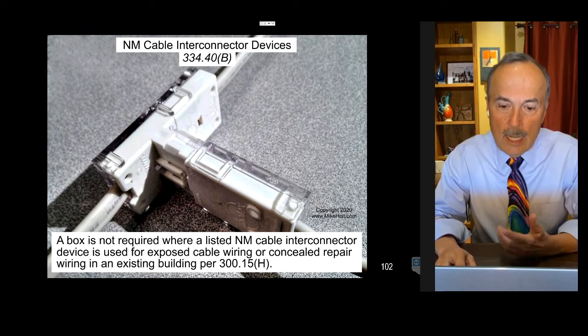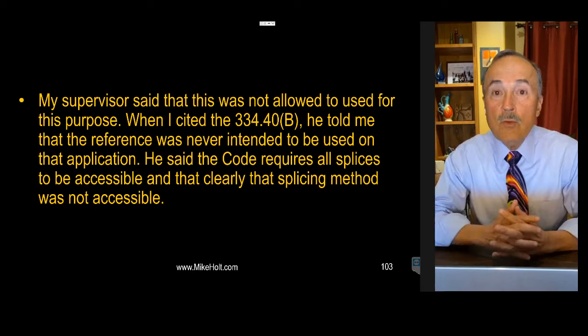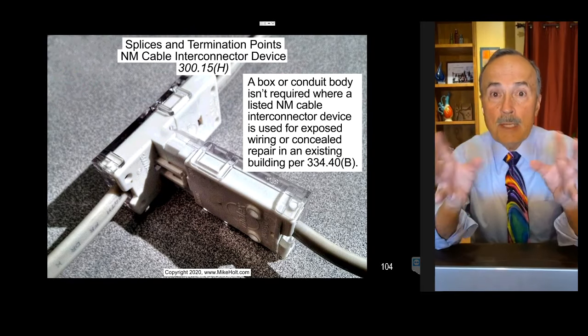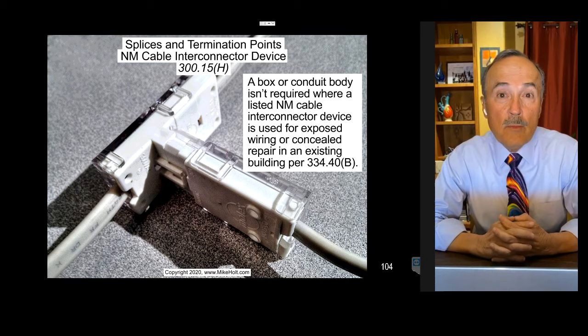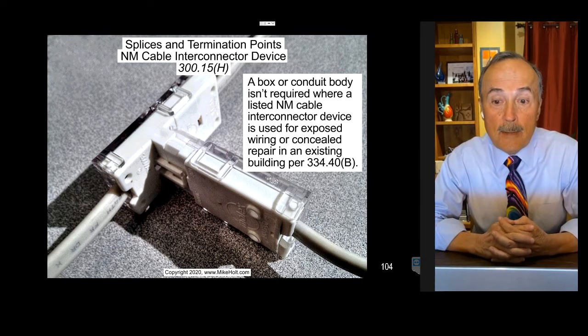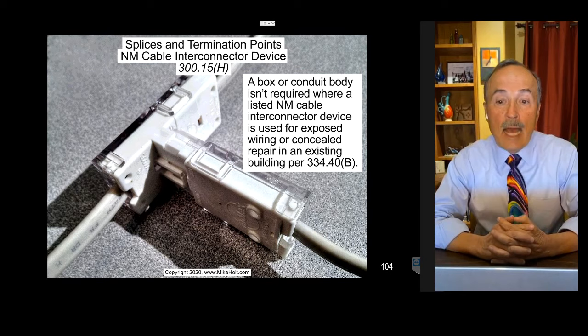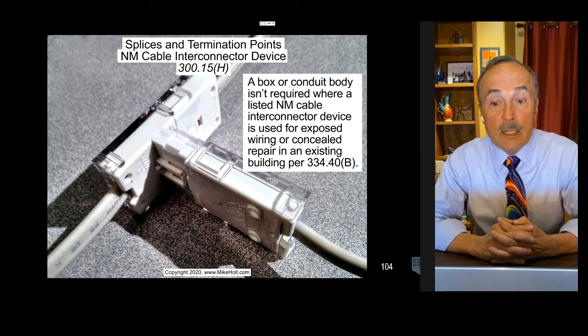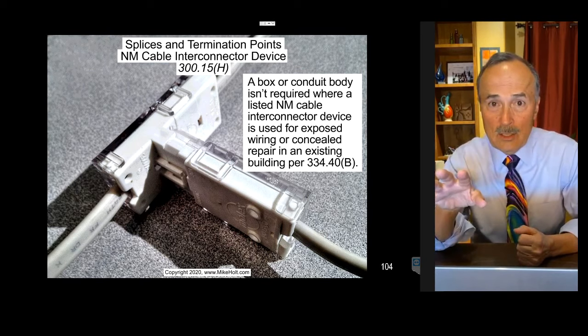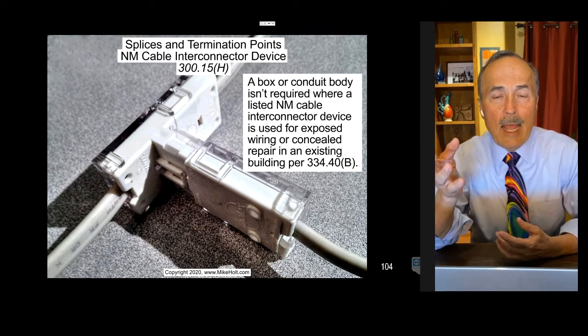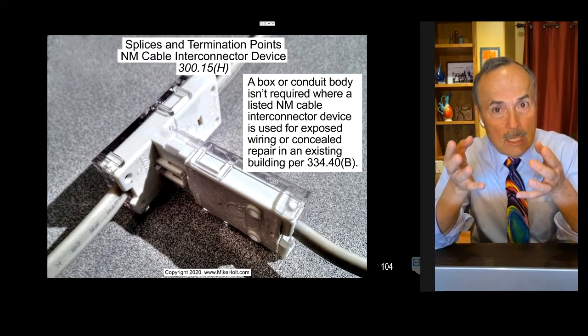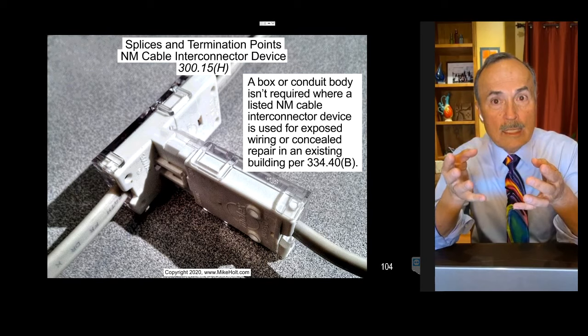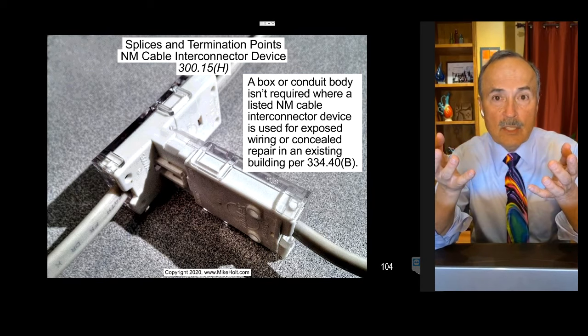I'm like, okay, well, you know what? The rule that talks about all splices having to be accessible also has a rule about this interconnecting, what do they call that thing? An interconnector device, an NM cable interconnector device. So the rules having to do with when you make a splice, it has to be in a box, has a specific rule, which is 300.15(H). Here's what it says. A box or conduit body is not required where a listed NM cable interconnector device is used for exposed wiring or concealed wiring repair in an existing building per 334.40(B).